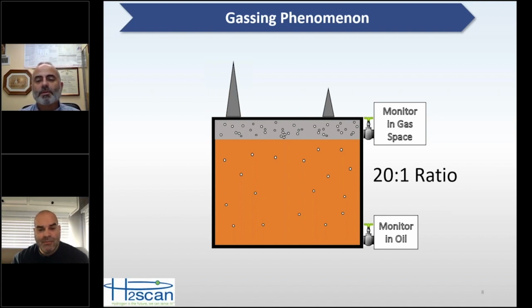And it's important to note too that most people are looking at the trends over time. IEEE just released the new C57.104, and it not only has the gas values as far as condition levels, but it also talks about rate of change, whether it's a daily, weekly, monthly, or yearly rate of change, and what values of the various gases you should be concerned about.